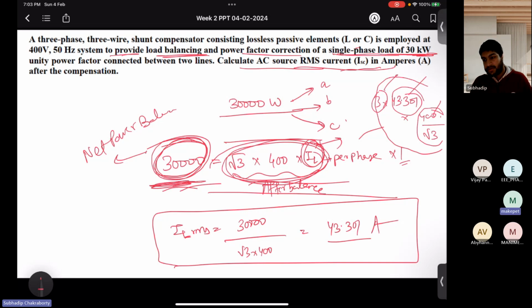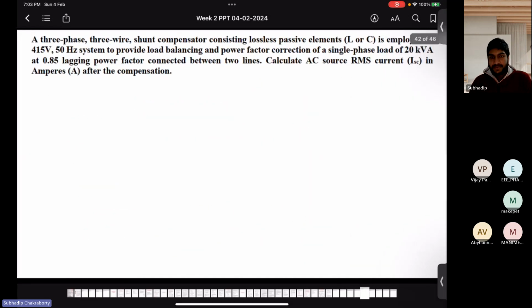So what your compensator has done is equally spread out the single phase load of 30 kilowatt among the 3 lines. Load is still single phase, but that loading is spread on the 3 lines, such that it appears to the line, or from the source end, as a 3-phase balanced system. Only for that we are using it. Okay, sir. Understood. So please don't get confused. This is very simple. That's why we do the compensation and the load balancing. That is the whole purpose of it.